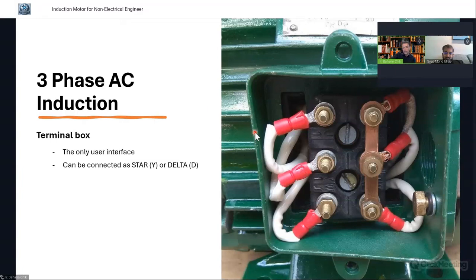So we need to look at the data sheet to see whether this motor should turn clockwise or anti-clockwise, viewed from the drive end. You need to make sure it is correct, because sometimes the motor turns in the reverse direction, and that defeats the purpose. So this is part of the commissioning check.